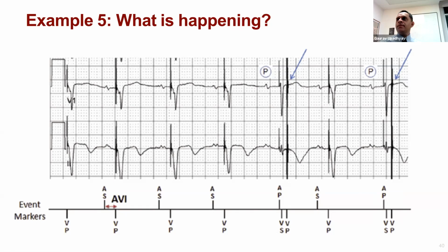Okay. So comments here, forced ventricular pacing and CRT or protection mode. All good ideas. So this is an example of a behavior that you'll see across devices, and it's called safety pacing. And it's a feature that was developed to prevent asystole due to crosstalk. Okay, so let's unpack what those words mean.